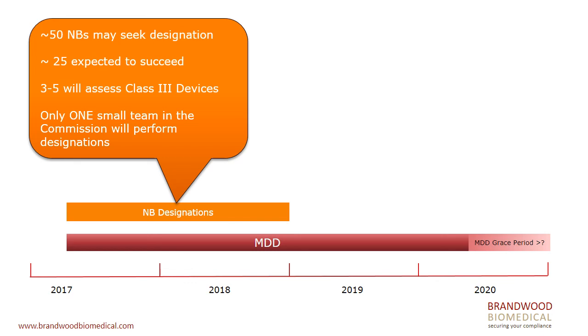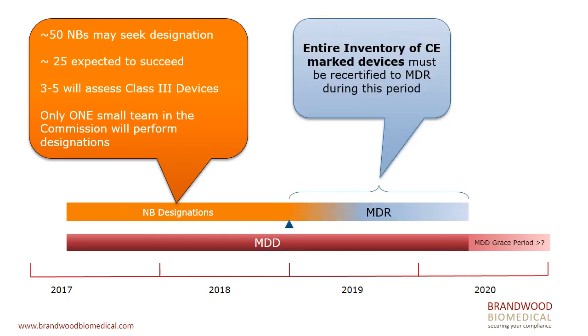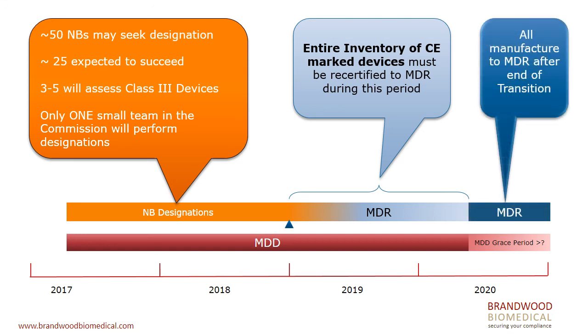That chews up about half of the transition period, which means we effectively have to recertify all of the CE mark devices in about an 18-month period, because there's no grandfathering. Everybody has to be recertified under the new medical device regulation. So it's going to get kind of busy from the end of 2018 onwards, and once the transition is over, all manufacturing must be done under MDR certification.